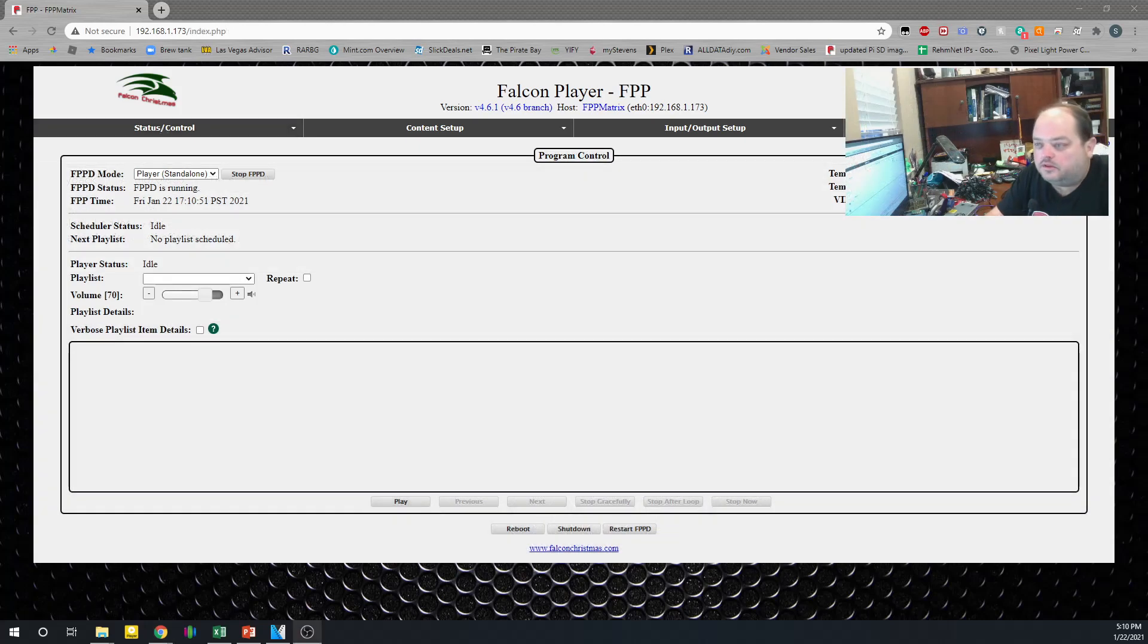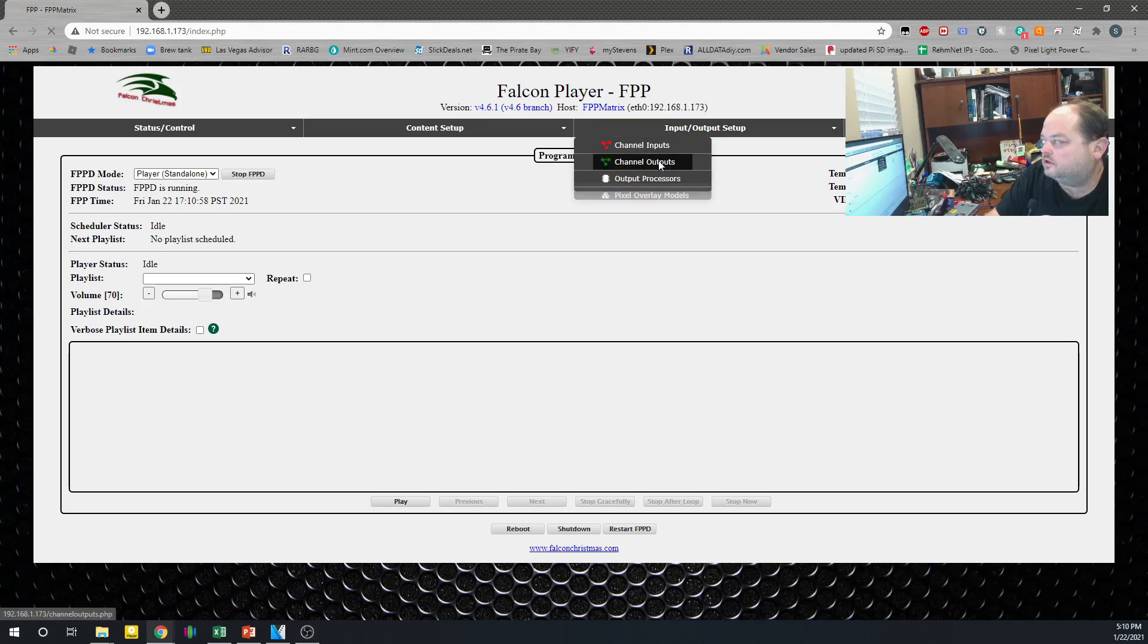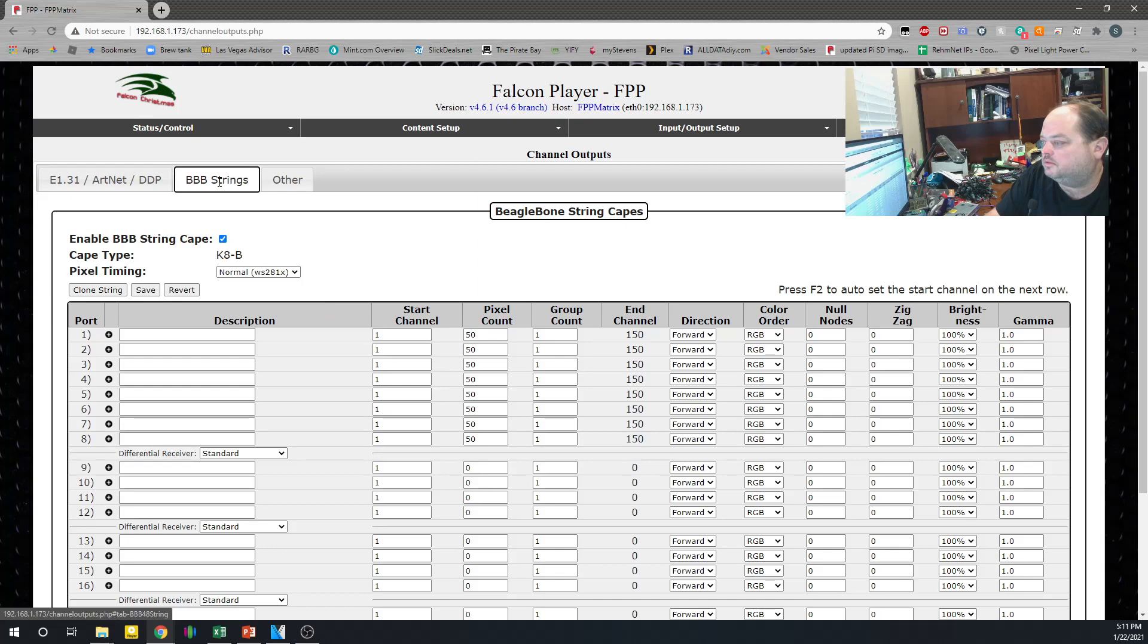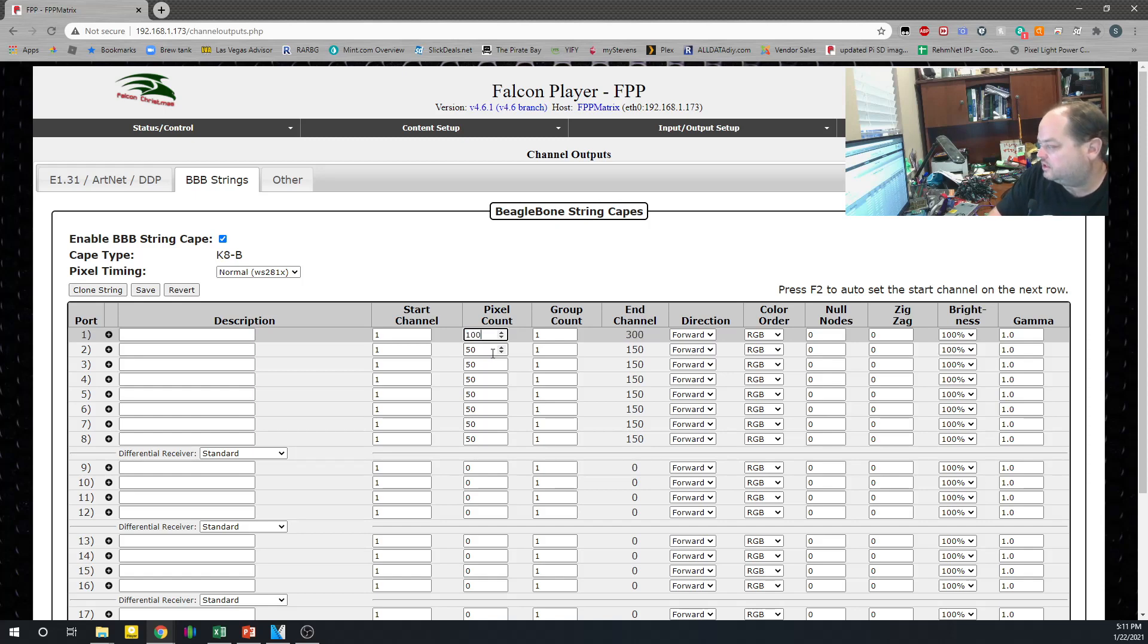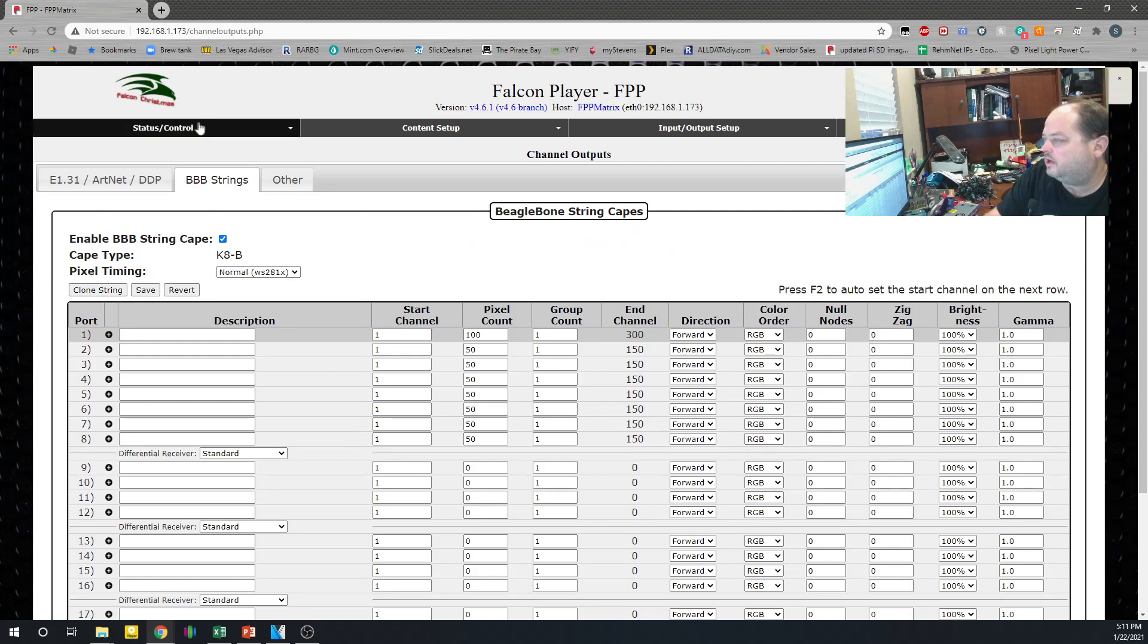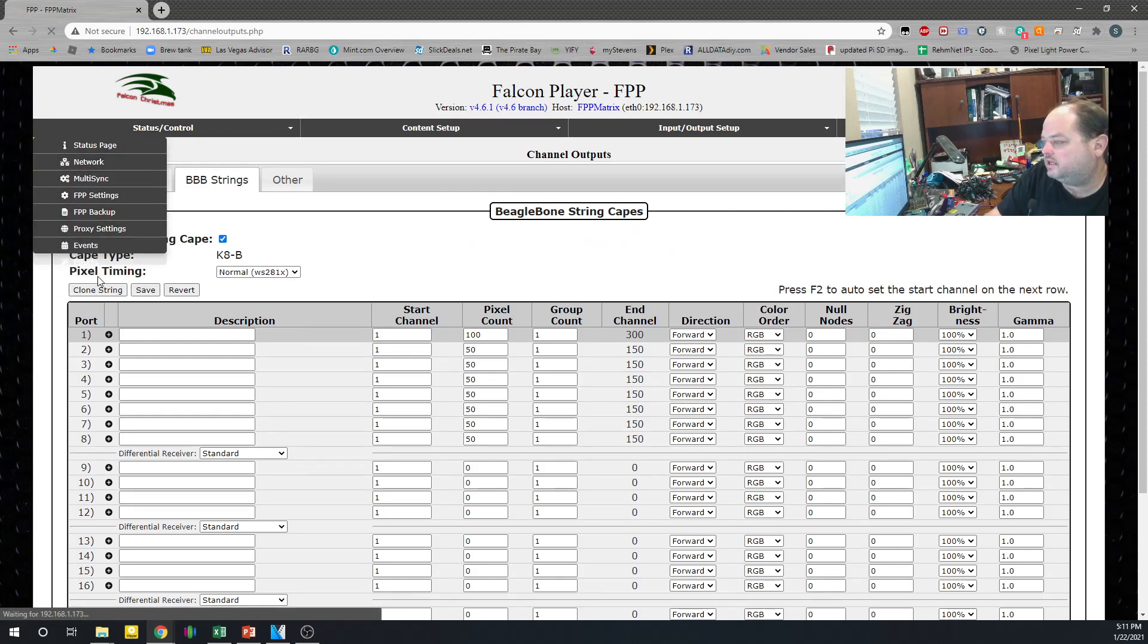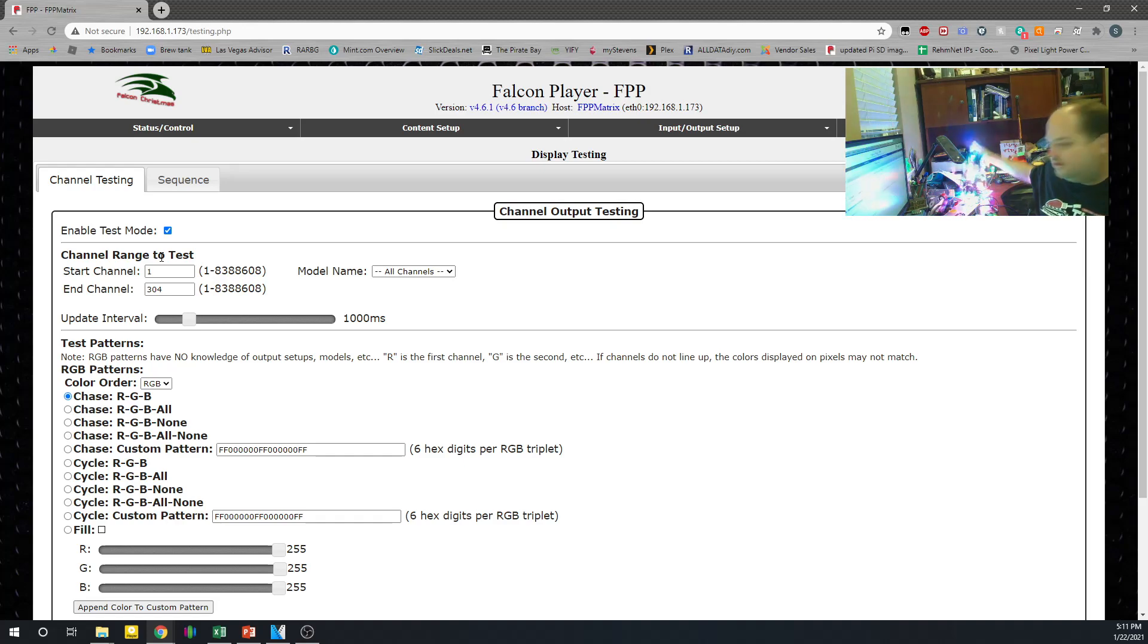The other thing that will be important for us to check here is the inputs and outputs. In particular, the BBB string. So we've got our light set up on port 1. You can see that the default is set to 50 pixels. That's why earlier we only saw half the string light up. It's a 100 pixel string. We'll change that to 100. Click Save. And now we can go to Display Testing. Click Enable test mode. And all our lights are lit up. Awesome.